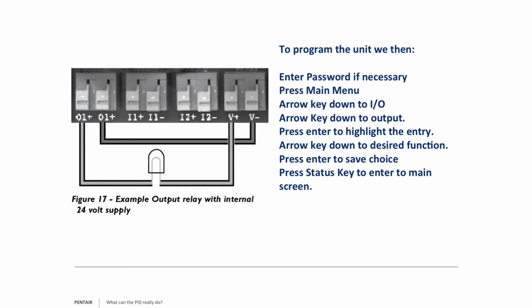Now again, when you hook up an output, wiring it is only one half of the issue. The other half is now I have to tell this unit what I want it to do. So again, we might have to enter a password. If you see that little key symbol in the corner of the screen, that tells you it's locked. So hit the password key, enter the password, and enter. Then hit main menu. We're going to arrow key down again to I/O, inputs outputs. We're going to arrow down to the output now. And now we want to press enter to highlight because it will say unused.